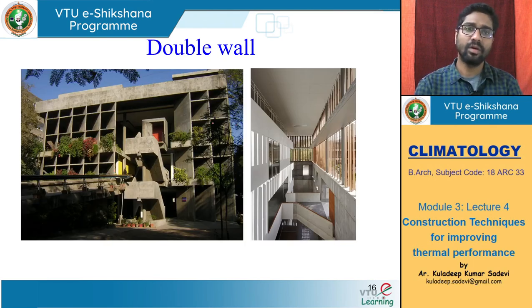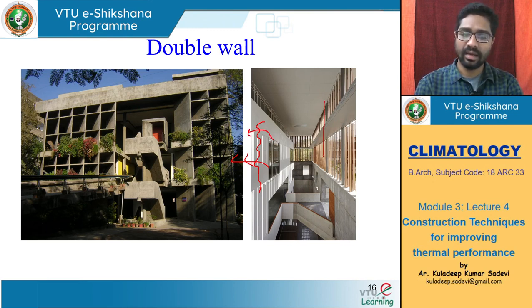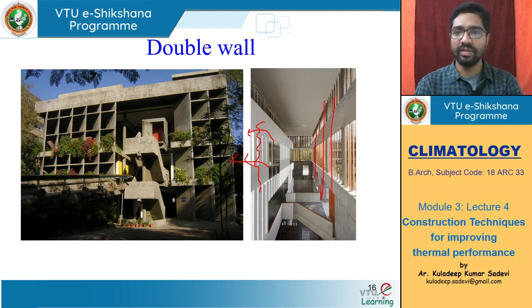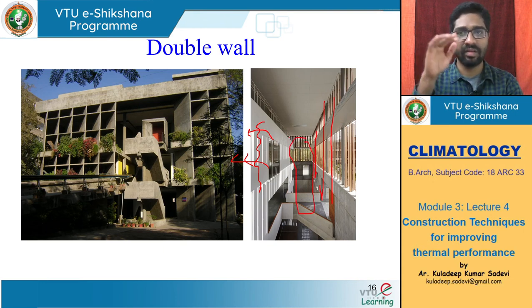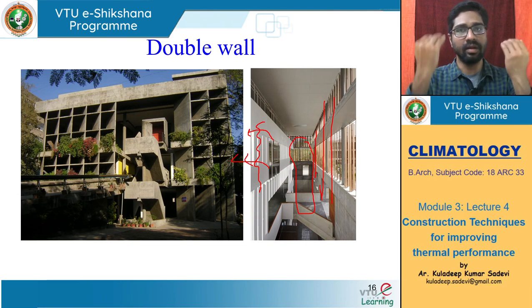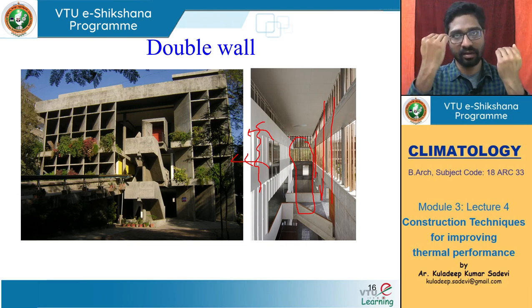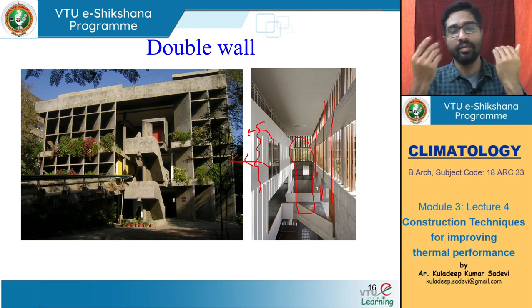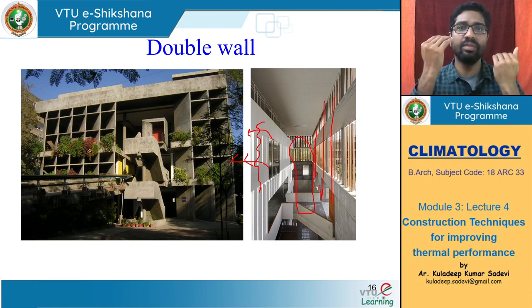Then there is the idea of a double wall, where you have an extra wall. The actual wall is where heat gain happens to the indoors. You add another layer of semi-transparent walls or shading layers, which cuts down radiation, and thus the temperature at the outer surface of the actual wall is well reduced. Your inner-to-outer temperature difference is already lesser, which means your decrement factor is lesser and the overall heat transfer is very much reduced. As we know, total heat flow Q = U × A × ΔT; if ΔT is higher, heat flow will be higher. By adding these layers, we cut down external surface temperatures drastically.